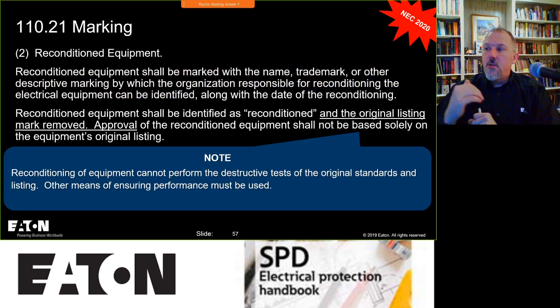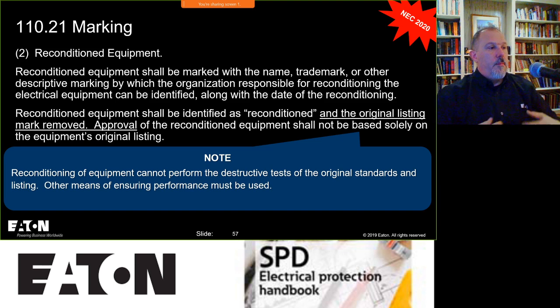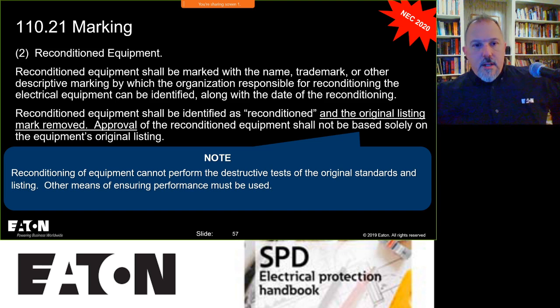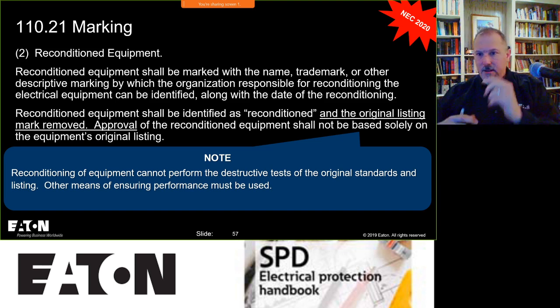So, reconditioning of equipment cannot perform destructive tests. The other thing they have in there is reconditioned equipment shall not be based solely on the equipment's original listing. The reason is because they can't do the testing that's done as part of a manufacturer, since we do a lot of destructive tests on a lot of different samples off the line. It's not going to happen on this.